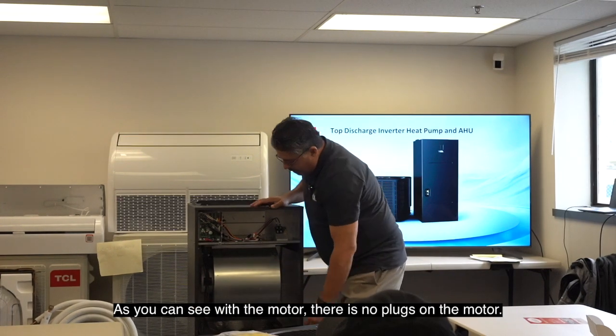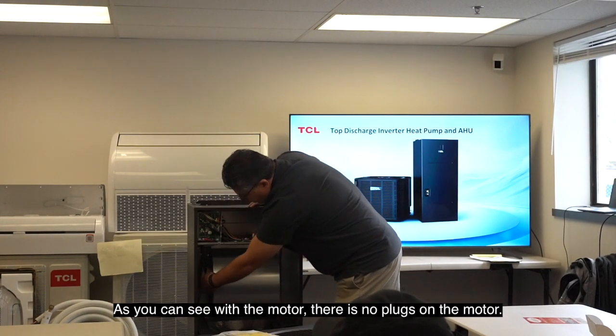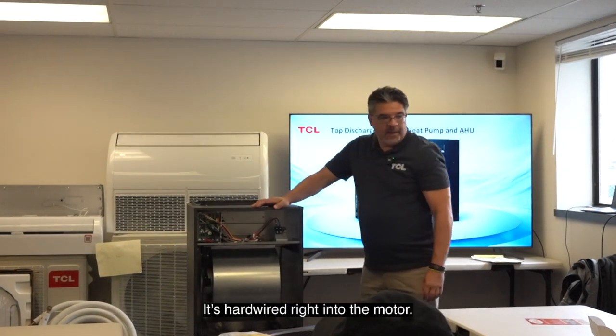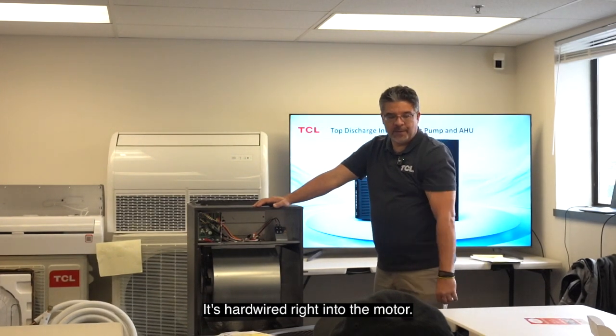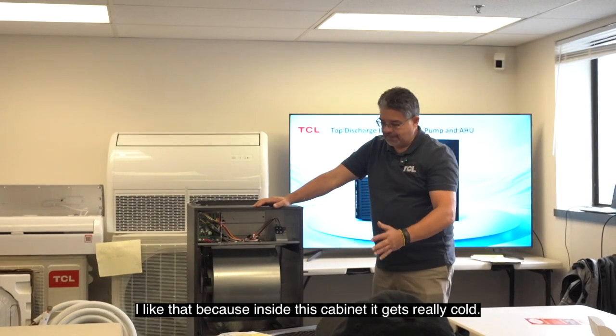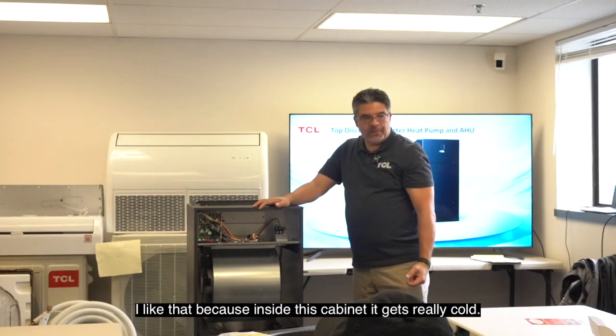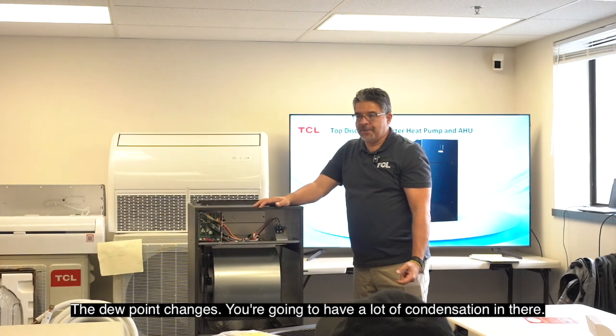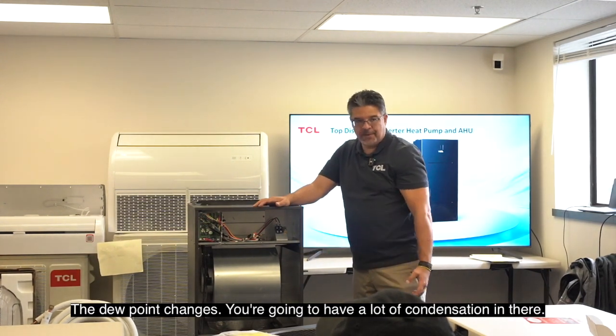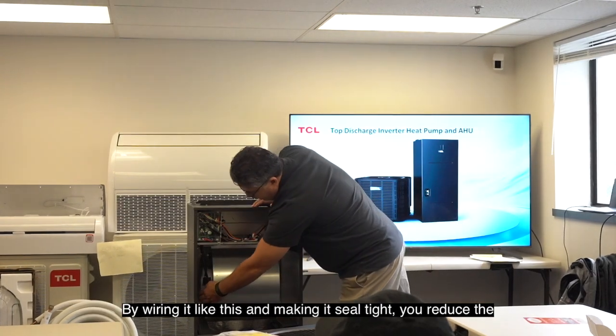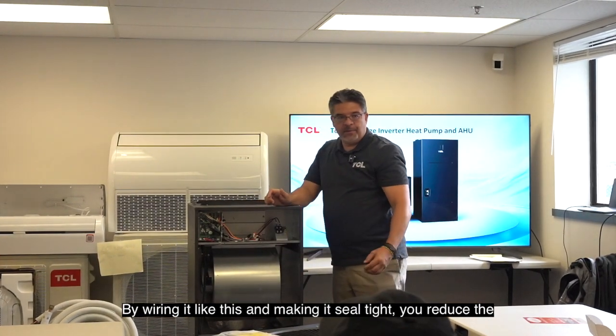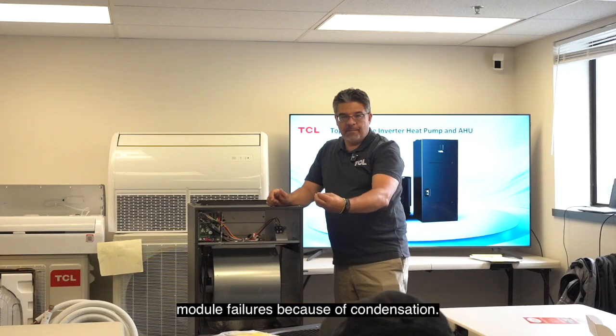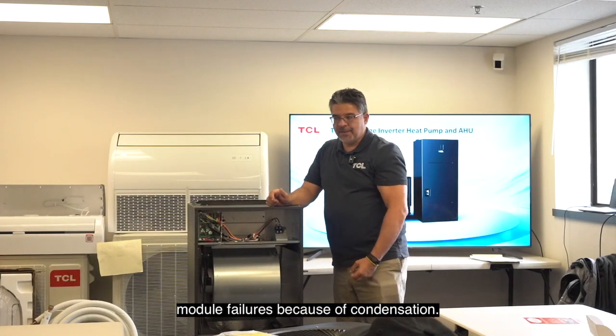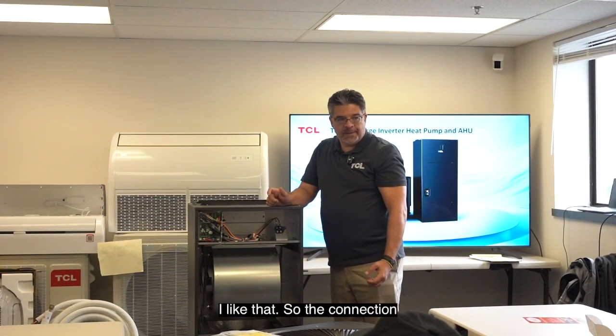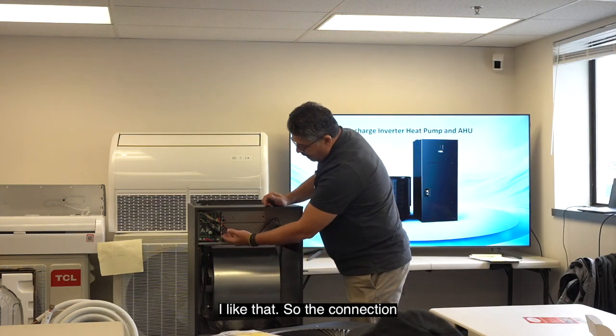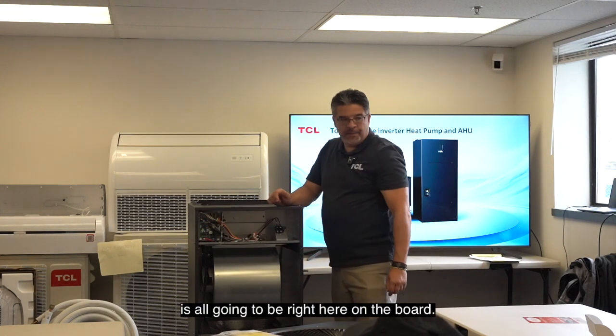If you can see with the motor, there are no plugs on the motor. It's hardwired right into the motor, which I like because inside this cabinet it gets really cold. The dew point changes and you're going to have a lot of condensation in there. By wiring it like this and making it seal tight, you reduce the module failures because of condensation, which I like. So the connections are all going to be right here on the board.